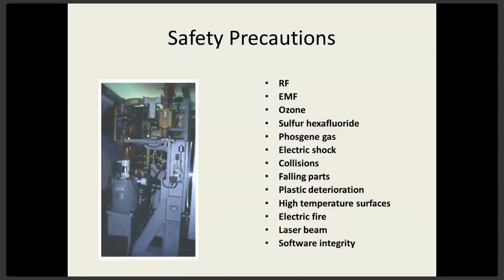Of course, there are collisions and falling parts. We always put things onto collimators that could fall off and hurt the patient if we're not careful. Radiation causes plastic to deteriorate. Deteriorated plastic is brittle; it breaks and cracks when it's bent and stressed. That is a hazard with long-term radiation exposure. Some surfaces within the machine get very, very hot. Electric fire: I've observed a couple of times, if solenoids get stuck and current is still passing through them, there's actually smoke pouring out of the machine. At that point, you hit the main circuit breaker and call the physicist.